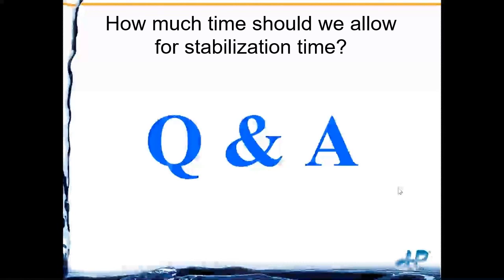Question: how much time should we allow for stabilization? If you've cleaned with something strongly oxidizing or strongly reducing, a 30-minute window is a good rule of thumb. After that, placing it in your ORP solution should only require 2 to 5 minutes. If it's taking longer, you probably need to clean it — ORP calibrations should be much quicker than pH because it's just a piece of metal.